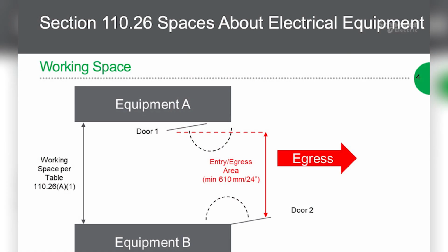Yeah, the electrical room is my biggest concern. With multiple equipment lineups, we can have pieces of equipment that face each other, and those opening doors could intrude into each other. That's a great point. When we think about multiple equipment lineups, there are many additional configurations to look at. We have a graphic for that as well. In this illustration with facing lineups, you have to consider open doors in both lineups, and whether you still maintain the 24-inch egress path that's required.